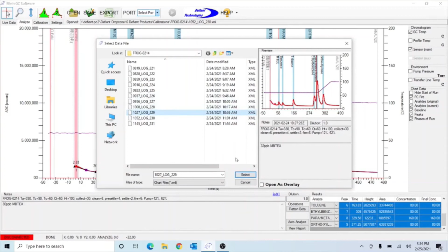Exact same procedure. Auto analyze. Now it knows where everything is, so it's going to fill that part out for me. All I have to do is correct the concentration. 32, 32, 32. For the purposes of calibration, notice it has little guesses in there for you. Ignore that. You are the human, you're doing a calibration, you are telling the software what the calibration is.